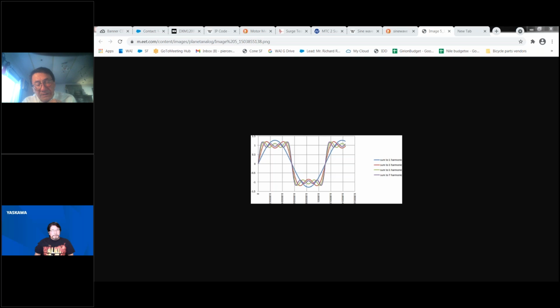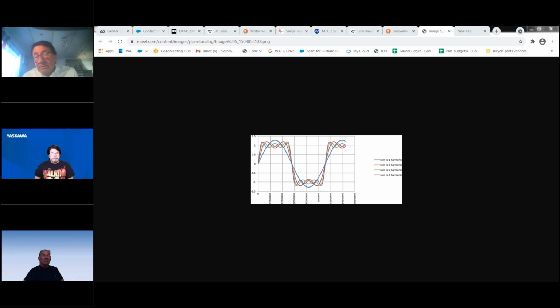What Craig came up with was something even more interesting. The issue of riding through the harmonics on the waveform that the VFD sends to the submersible motor. Initially, we thought, oh, okay, that's understandable because the motor's long and skinny. It has less inertia. But what Craig brought to light is that the problem was even more exacerbated by, one, the fact that the federal government energy efficiency standards caused the motors to be redesigned so that they have a slightly higher full load RPM, causing them to go faster, and in a pumping application, that means they're going to draw more power by the cube, if you will.